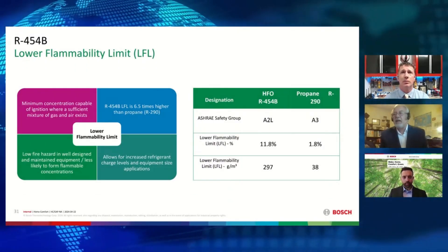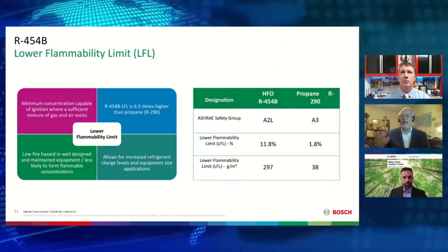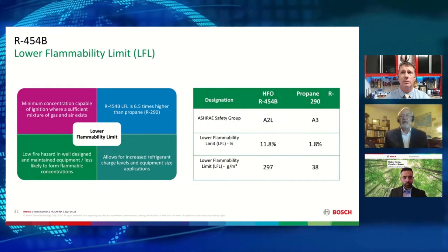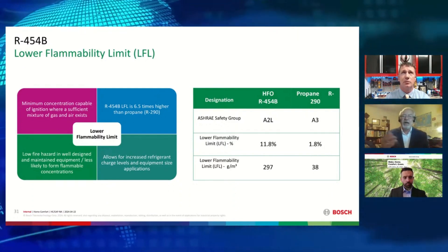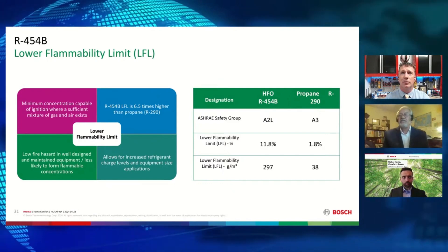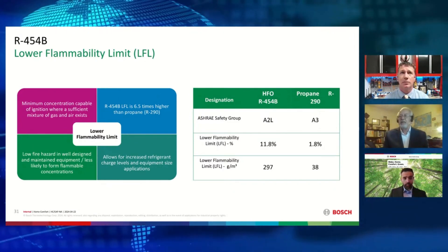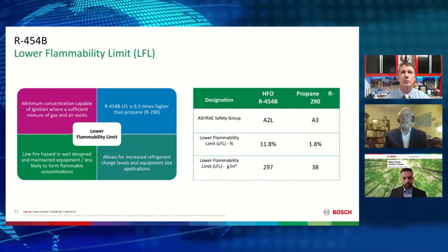In this particular slide, remember that refrigerants like R-454B will have a lower flammability limit — as we just talked about — that indicates the minimum concentration capable of ignition, where a sufficient mixture of the gas, the vapor, and the air exists. The lower flammability limit is very important for equipment design and for safety. It's simply expressed as a percentage by volume, with a higher rating being better.